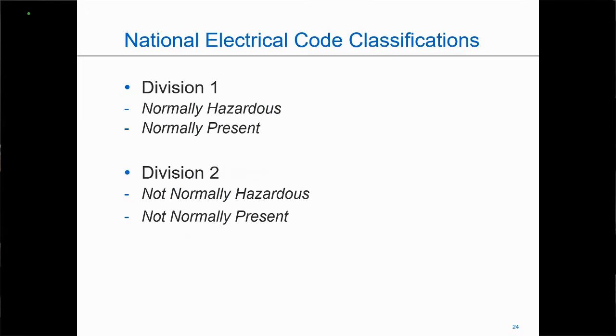But the next thing we're going to want to know is whether our area is Division 1 or Division 2. So Division 1 is considered hazardous under normal operating conditions. Division 2 takes a fault condition to become hazardous. So an example would be if we had a paint booth and we were spraying a piece of equipment in the paint booth. Under normal operating conditions, those spray vapors are going to be present. So that'd be a Division 1 area. Now, maybe next door is an area where they're storing a lot of the pigments, chemicals, and paints that are used in that spray painting application. For that particular area, one of those canisters or drums would have to leak for the gases to become present. So it would not normally be hazardous; it would be a fault condition for those particular gases to become hazardous.